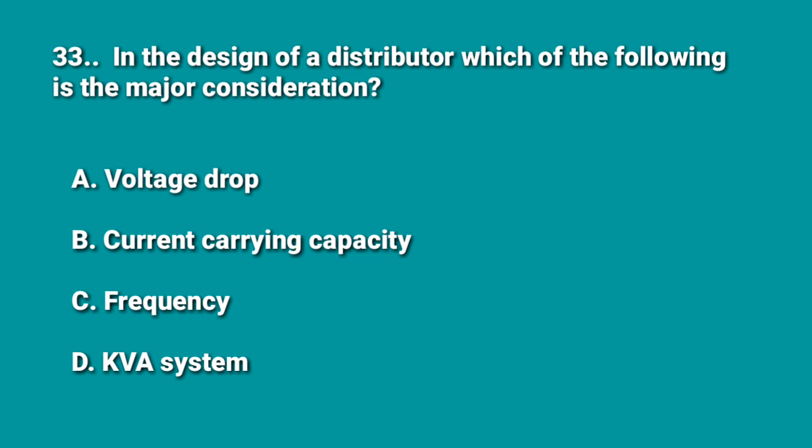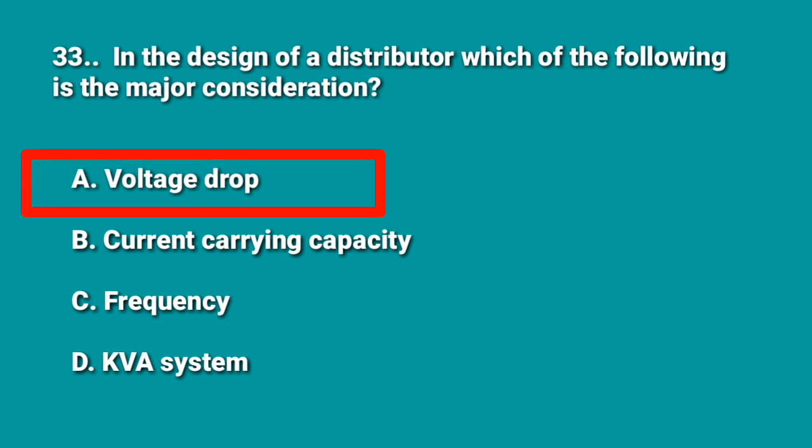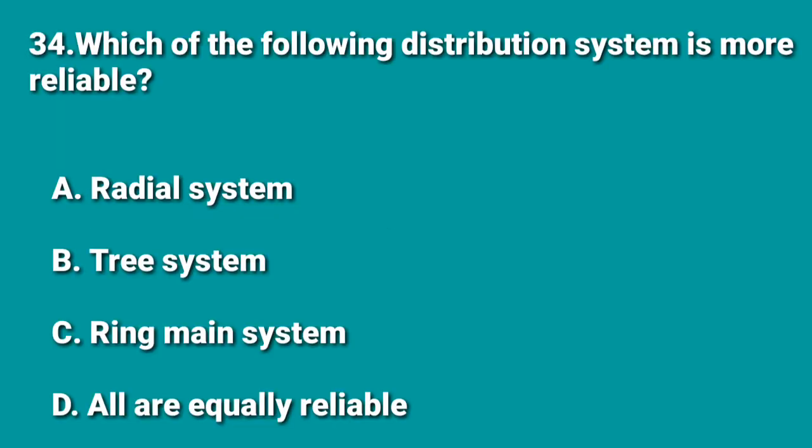In the design of a distributor, the major consideration is voltage drop, whereas for a feeder the main consideration is current carrying capacity. Frequency and kV are not the primary concerns — current carrying capacity is the main focus for a feeder, and voltage drop is the main focus for a distributor.